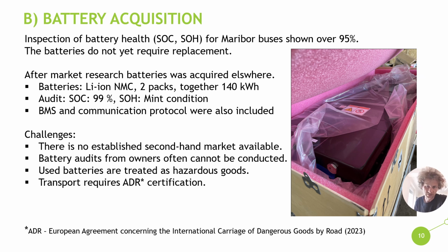The batteries used in the energy storage are Li-ion NMC. We have altogether 2 packs of batteries, together 140 kilowatt hours. Within the acquisition, an audit was made of state of charge and state of health, and it showed that batteries are in very good condition. The BMS, battery management system, and communication protocol were also included.